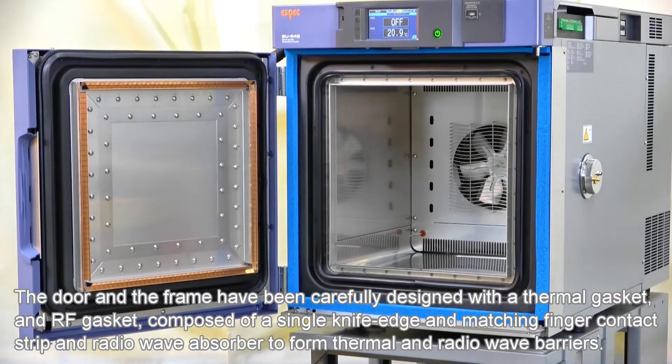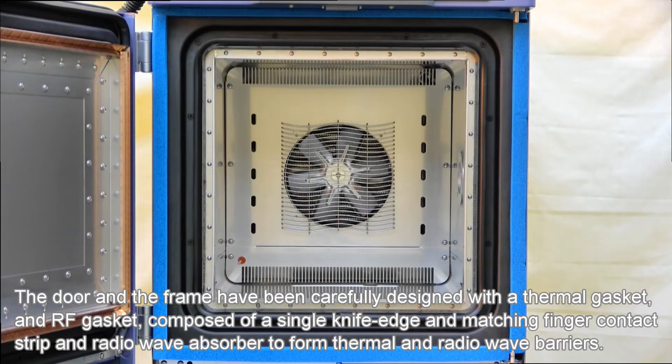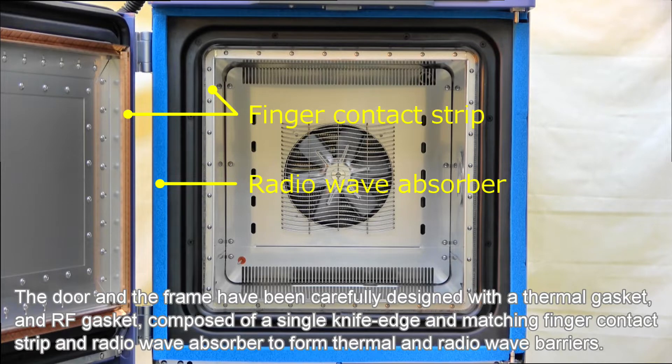The door and the frame have been carefully designed with a thermal gasket, an RF gasket, composed of a single knife edge and matching finger contact strip and radio wave absorber to form thermal and radio wave barriers.